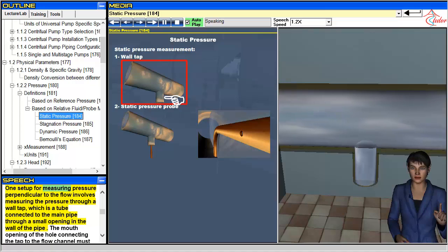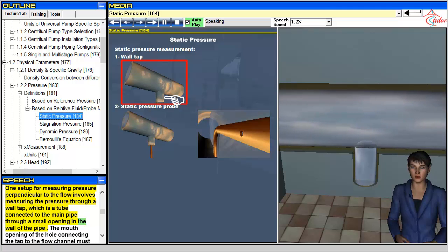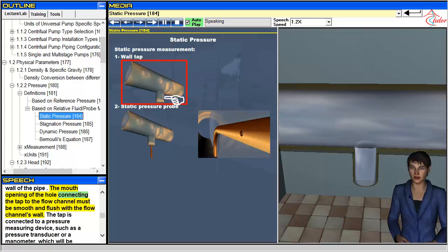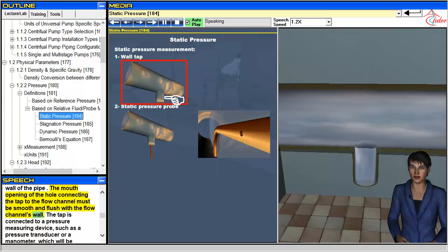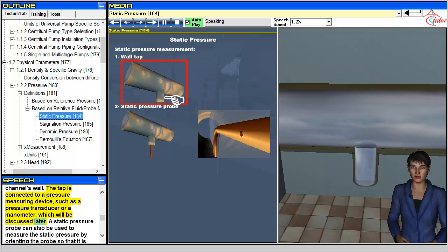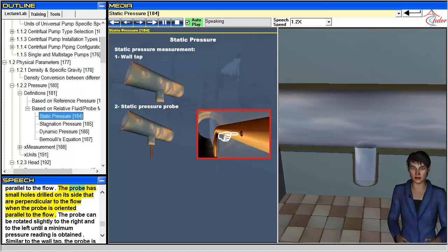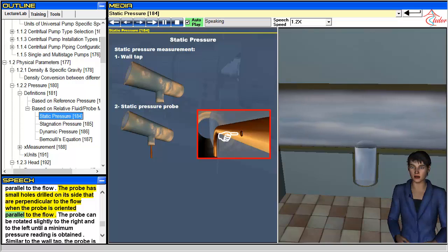One setup for measuring pressure perpendicular to the flow involves a wall tap — a tube connected to the main pipe through a small opening in the wall. The mouth of the hole must be smooth and flush with the flow channel's wall. The tap is connected to a pressure measuring device such as a pressure transducer or manometer. A static pressure probe can also be used by orienting it parallel to the flow, with small holes drilled on its side perpendicular to the flow.